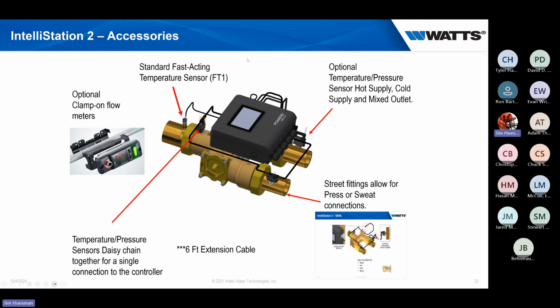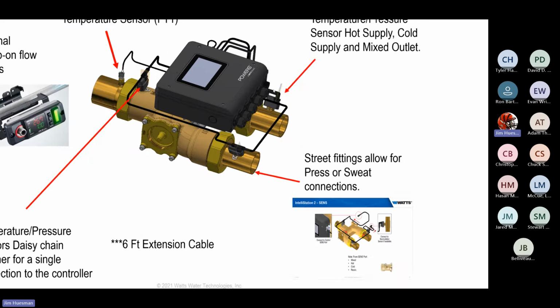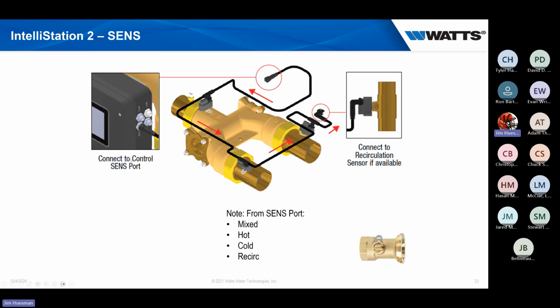What's nice is they've made it really simple when we tie these in, you don't need to cut new T's, new ports, and have the right size. Because if I have a sensor here and my tip's only sitting out maybe half an inch, I'm not going to be able to cut in a 1-inch T and add a 1-inch female adapter. Our sensor would never hit that. This was brought up by some of the contractors, that we should add ports so we can add different features later down the road. And that's what they've done.